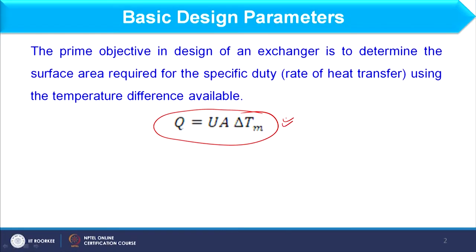Is there any other equation for heat transfer? Yes — we also relate Q = m·Cp·ΔT. Q is the heat duty, meaning the capacity to transfer heat from one fluid to another. That should be in balance: the m·Cp·ΔT of one fluid should equal m·Cp·ΔT of the other fluid. So, we have two basic equations: Q = m·Cp·ΔT and Q = U·A·ΔTm.